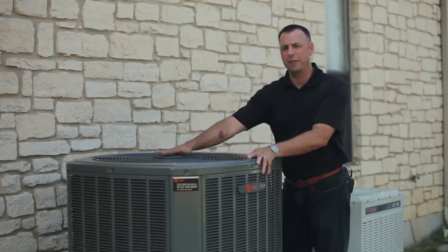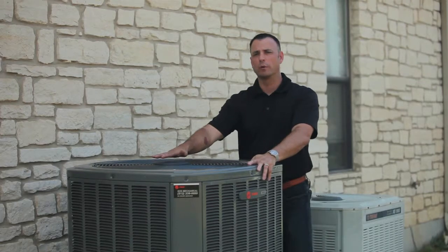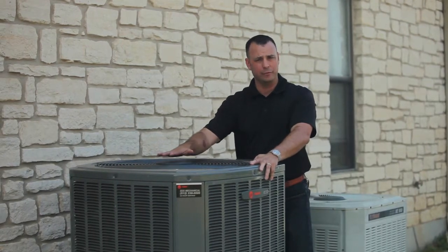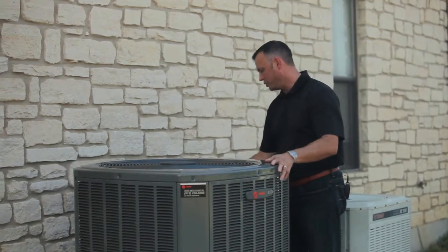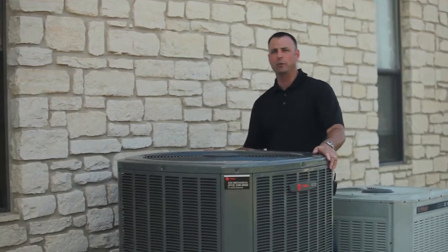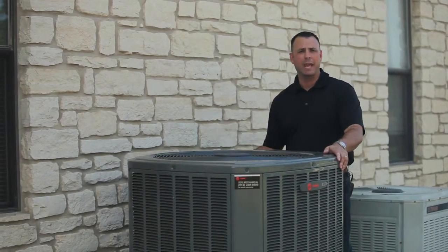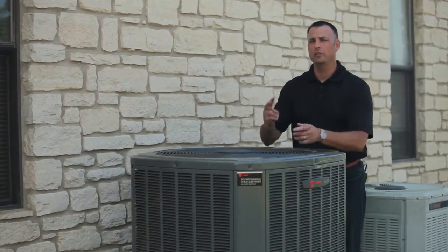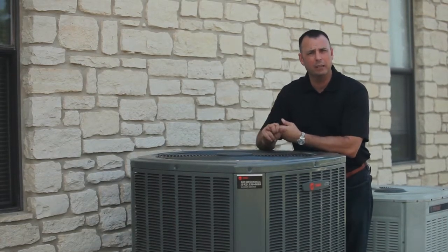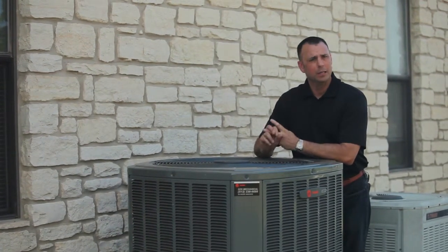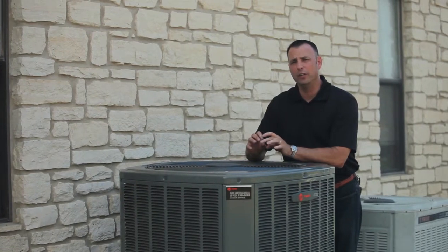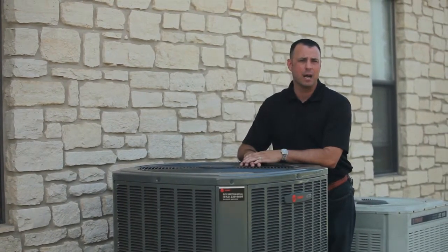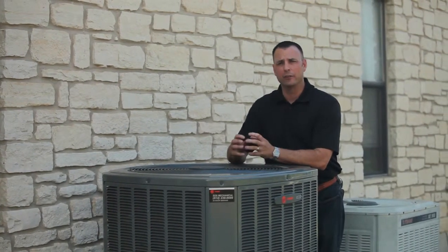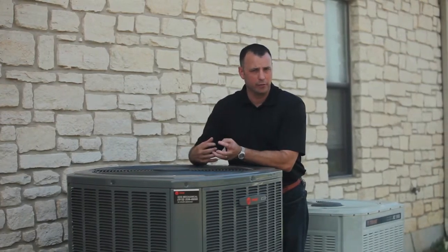You've got a condenser fan motor out here - some of those motors require oil, so he would oil it if needed. You're also going to have a charge, which is the refrigerant within the unit, so he's going to put gauges on your system and check either a superheat or a subcooling. That gives him an overall view of how well your unit is operating, and whether or not you need refrigerant.